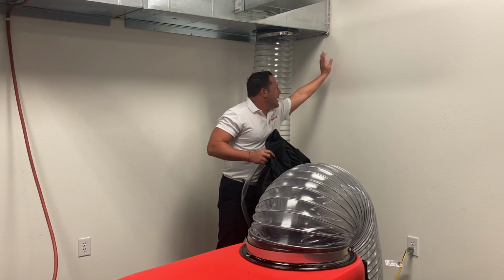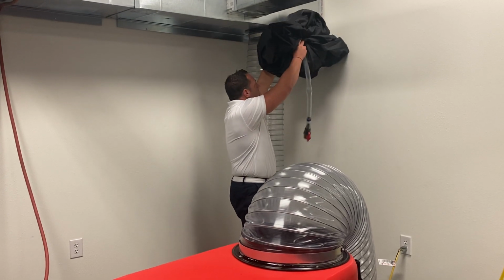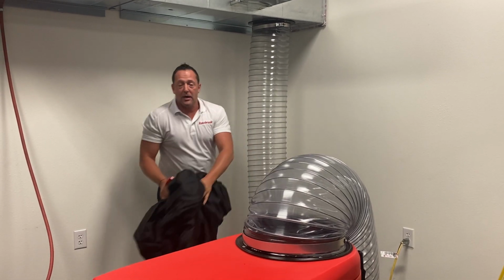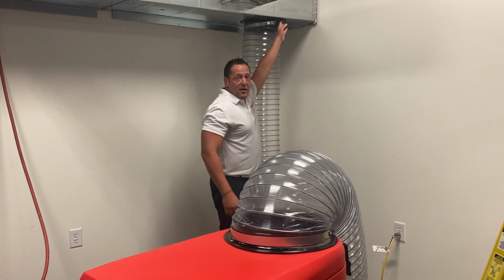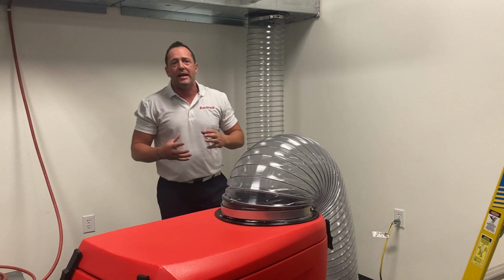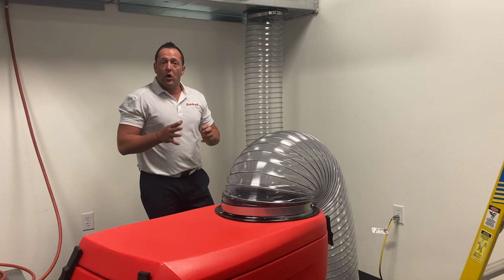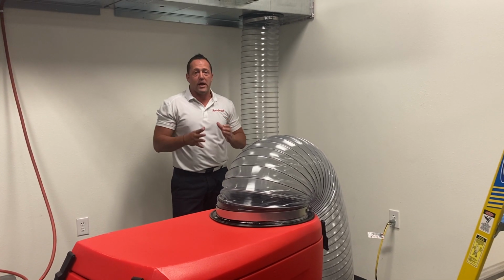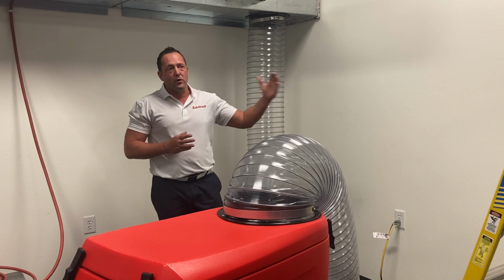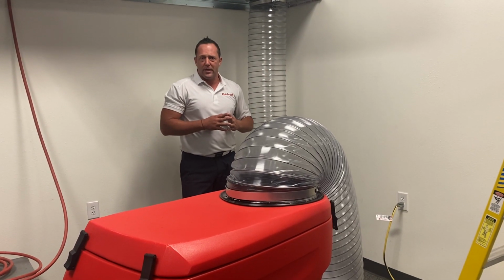So you can imagine the air bladder being on this side of the hole, the access hole that we cut. What I'm going to do is insert it inside of there, and then using compressed air, I'm going to blow it up. Now it swells off, and it becomes a barrier from my vacuum to the air handler. Now, I've seen videos where you have pogo sticks, and they're great ideas to be able to clean hard to reach spots at times. But again, you're not getting around cutting an access hole into the ductwork using negative air because you have to create that barrier. I keep stressing it because it is that important. You don't want to impact those brand new coils if it's a brand new unit, or if it's an existing unit, you don't want to impact the coils with the dust and debris either.